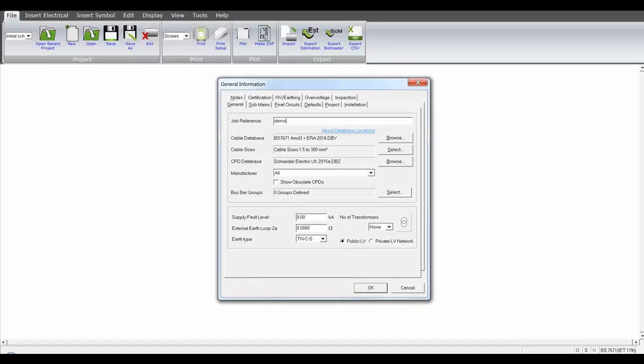The idea being to set up the basic parameters such as your preferred cable types, your preferred protection on final circuits or main submains, or setting up the various voltage drop on submains and final circuits. So you're setting up the worst case scenario. So if, for example, 80% of your submains are copper XLPE armoured cables, you would make the selection here and then change any other cables that are different to that on a cable by cable basis. So all cables can be controlled individually. All we're doing here is setting up the defaults.